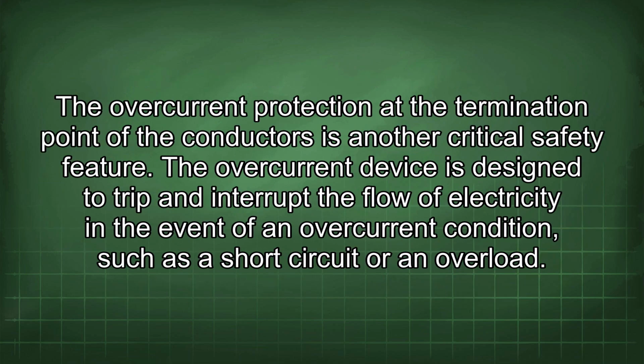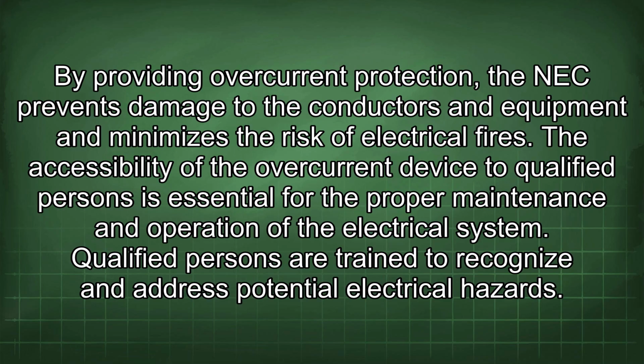The overcurrent protection at the termination point of the conductors is another critical safety feature. The overcurrent device is designed to trip and interrupt the flow of electricity in the event of an overcurrent condition, such as a short circuit or an overload. By providing overcurrent protection, the NEC prevents damage to the conductors and equipment and minimizes the risk of electrical fires.